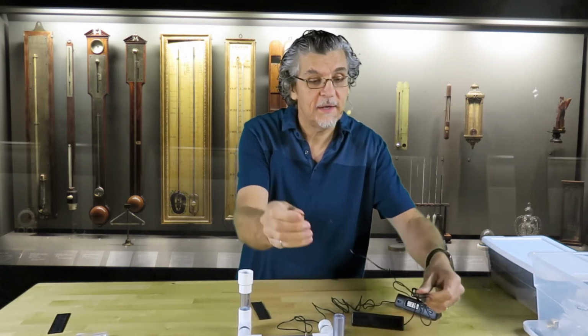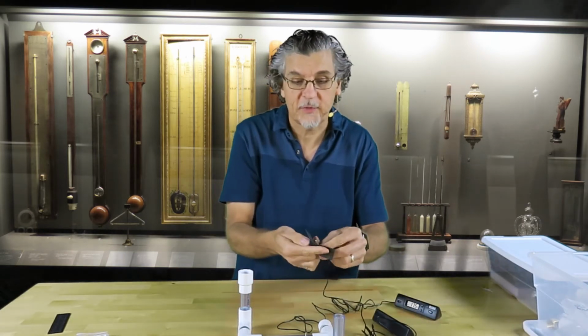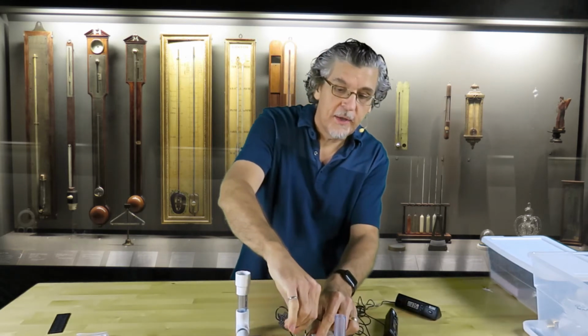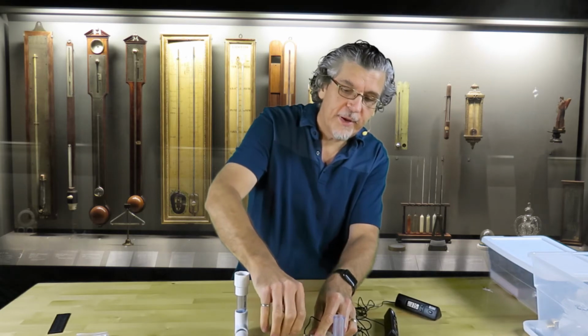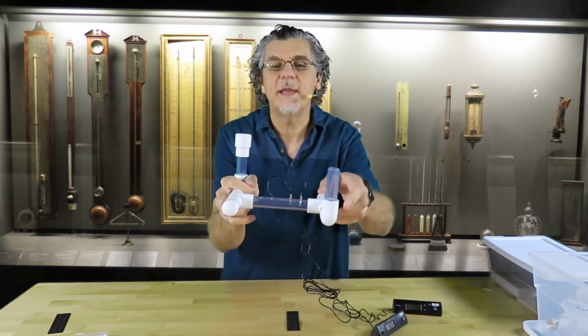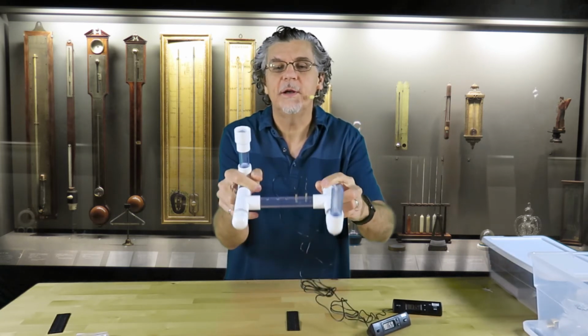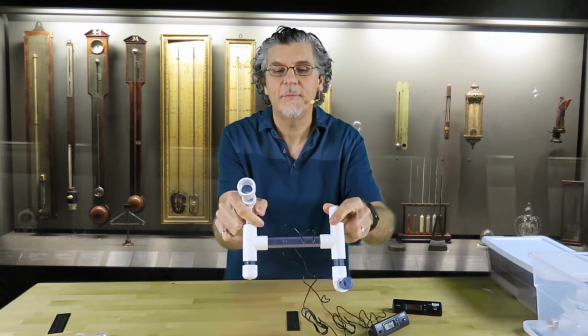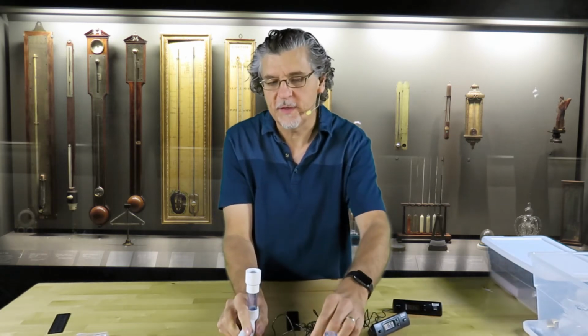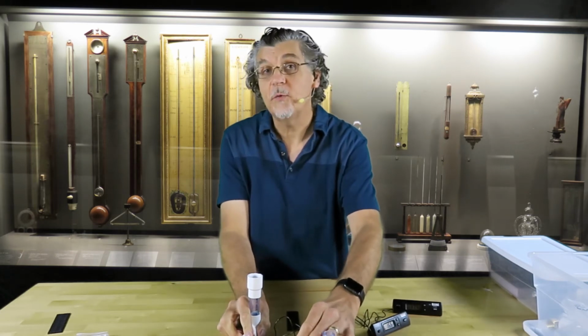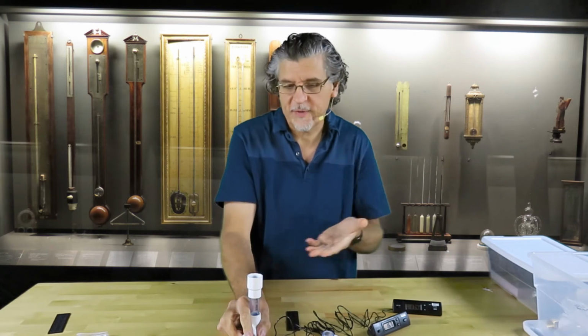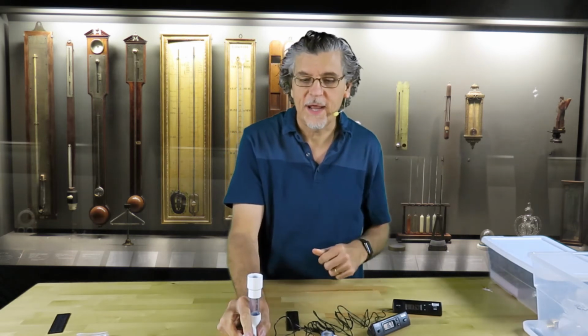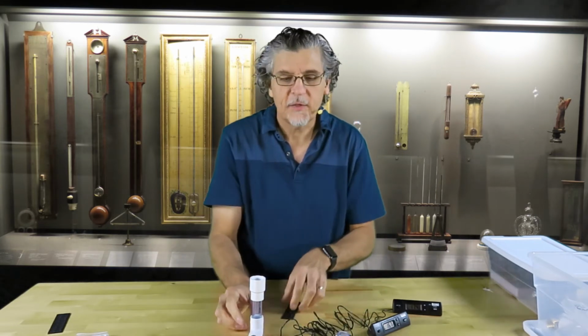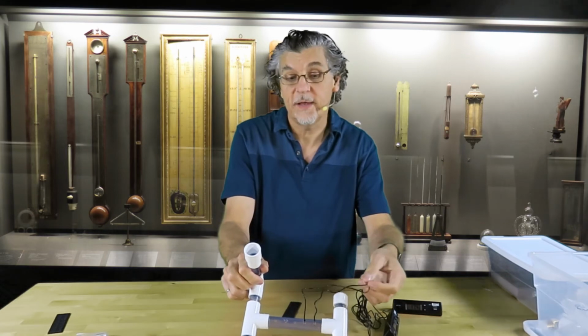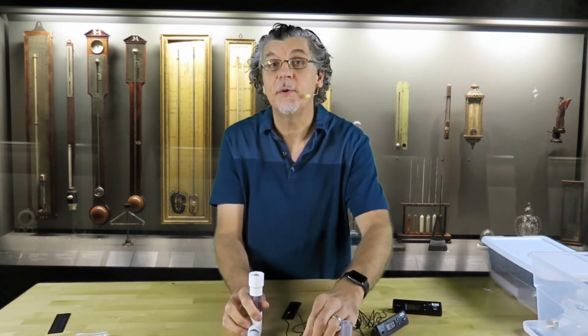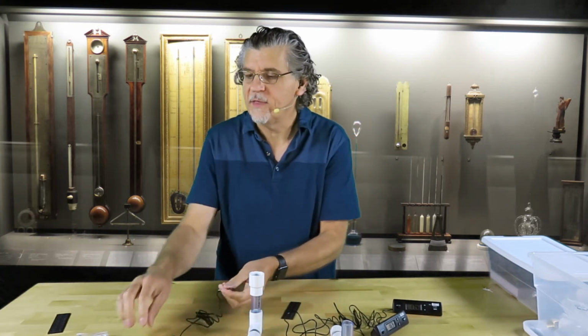I'll now take the second one, and again, I'll take my little black strip and put it around the NTC sensor. I push it into the second hole. That one was a little bit tighter, but you can see as I'm doing this that I'm not pushing the NTC sensors all the way in. There's still a portion of the NTC sensor sticking out of the pipe, and that should be fine to give you enough for the calibration. The reason you don't want to push it all the way in is that it makes it really hard to pull them out, because all you're then doing is pulling on the wire, and that will damage the sensor, so we don't want to do that. So you want to have a little bit of the silver, probably about 5 millimeters, exposed out of the pipe, making it easier for you to remove.